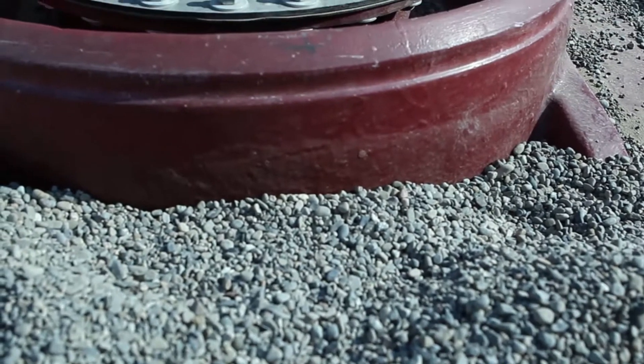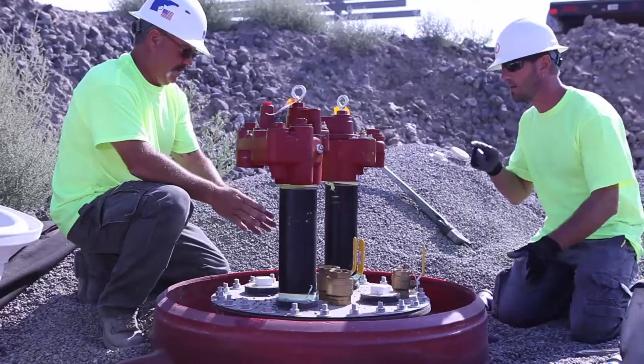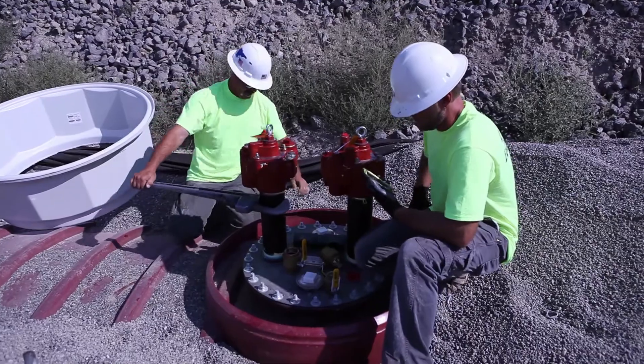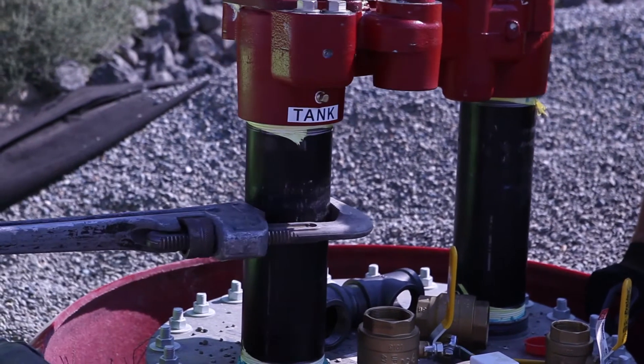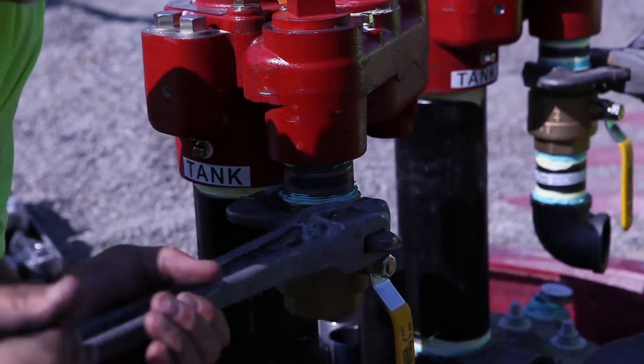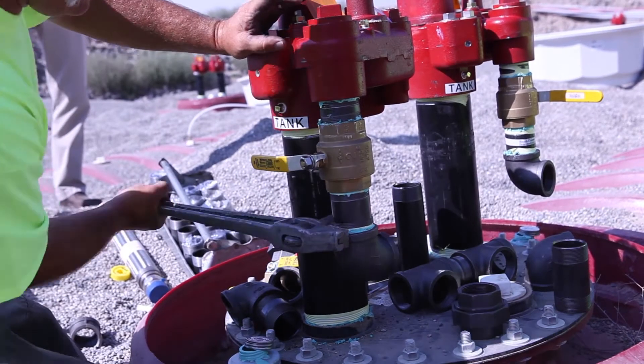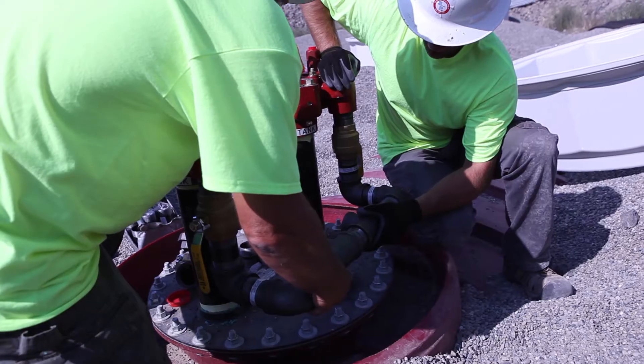In this install, we're actually manifolding two-horsepower pumps together to make sure that capacity is there. When you install two STPs into one sump, you do have some spacing issues, but all you need to do is put ball valves on the discharge of each so you can isolate one to work on it while the other keeps the site running. You then bring your piping down and manifold it together with T's and nipples to get the two or three discharges you want.